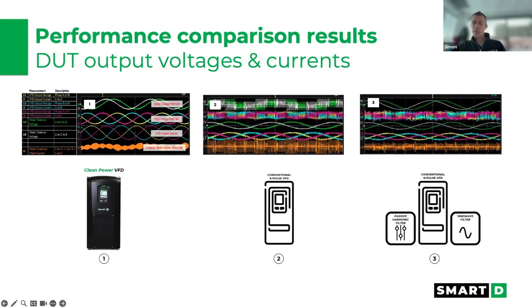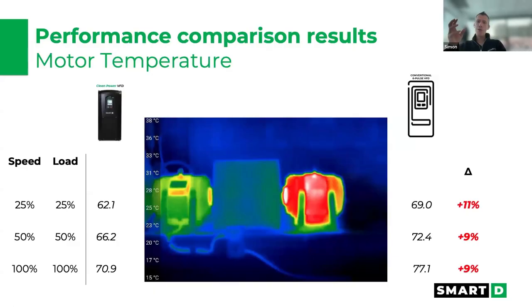Short of that, and of course, I don't know of anyone who puts in a sine wave filter purely for noise purposes, although actually that's not true. I know one job where that happened. You won't typically do that, but that's the only way to really remove that issue. And if you compare the impact of our clean power VFD with a standard PWM drive, you're going to measure about a 10% difference in temperature.